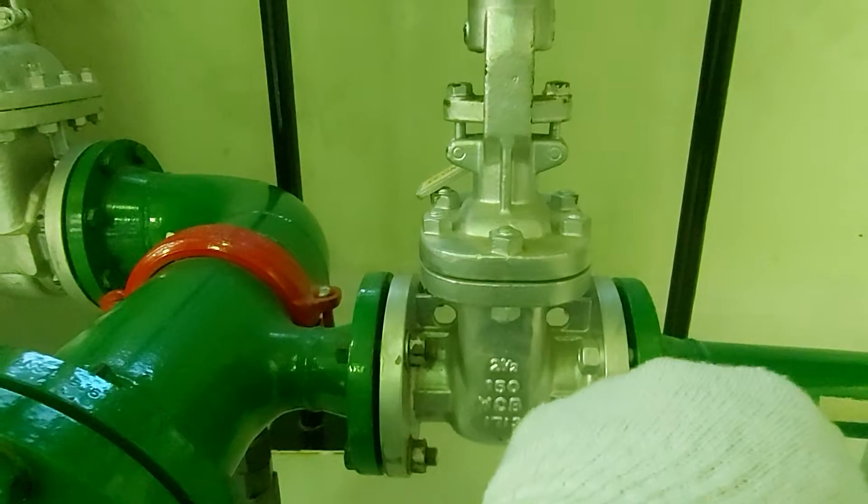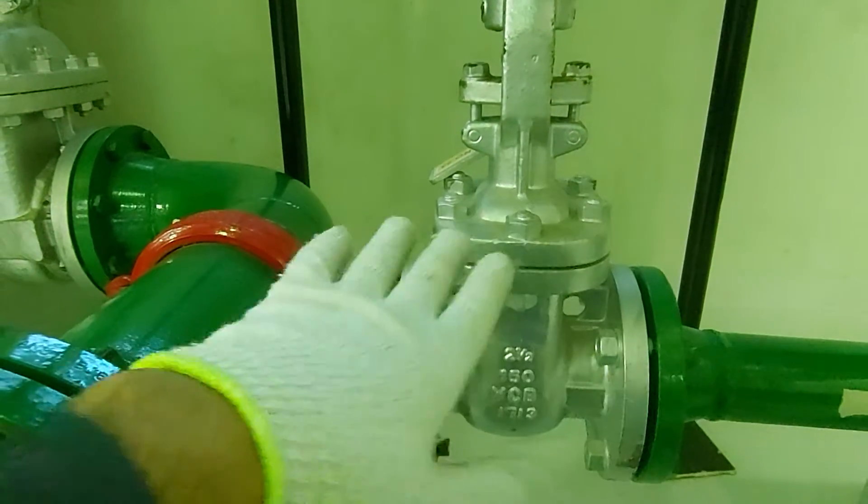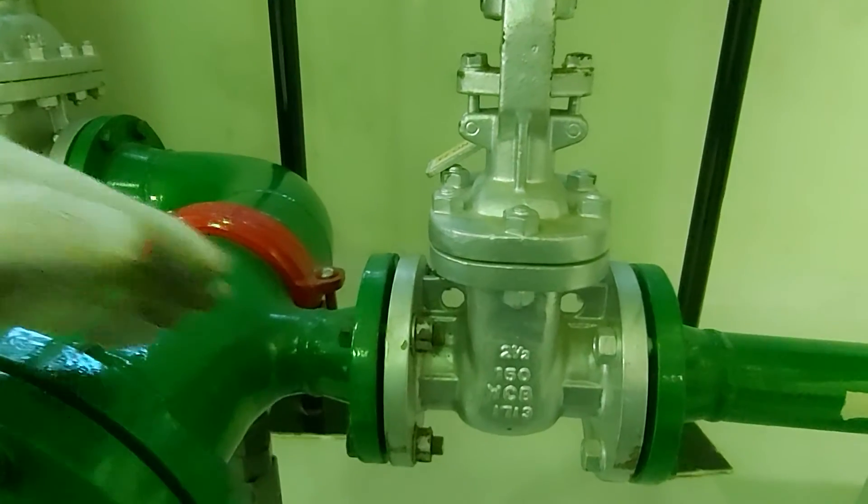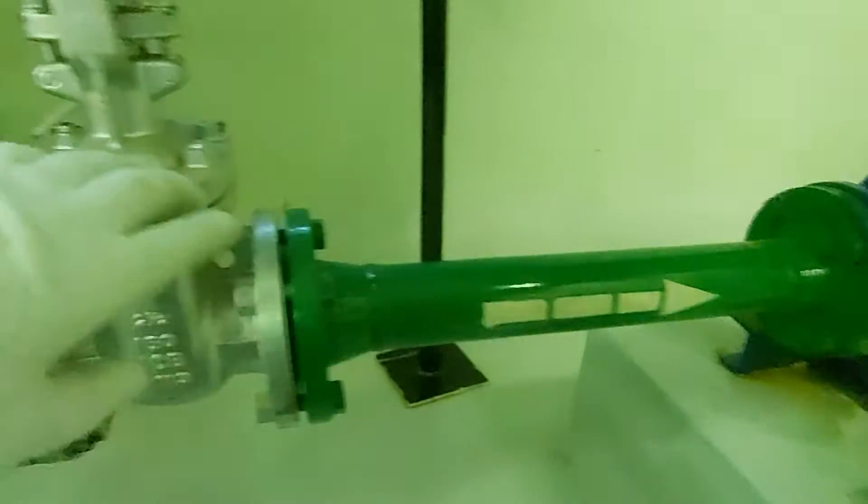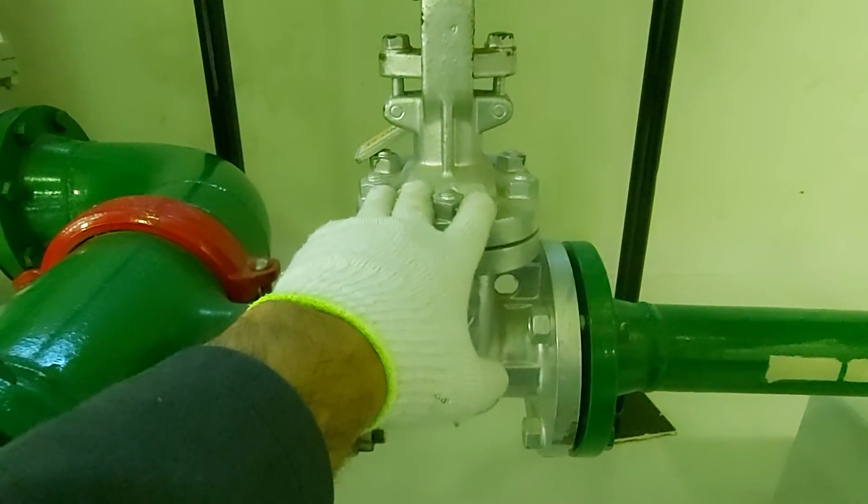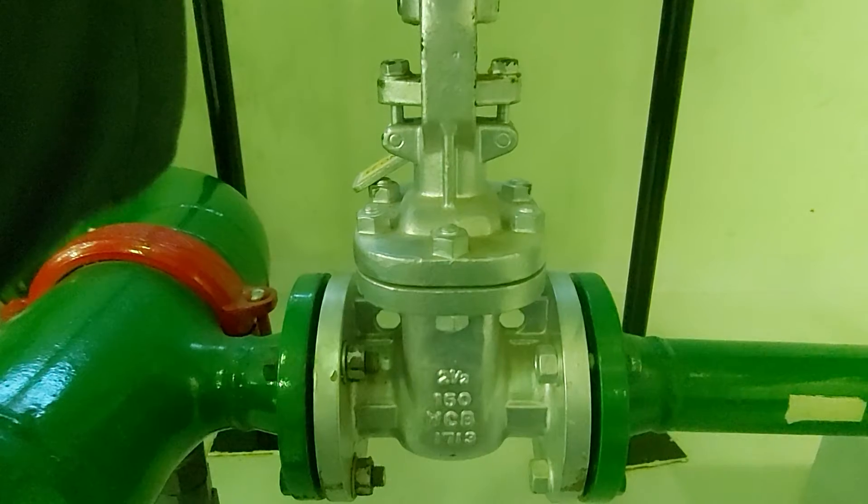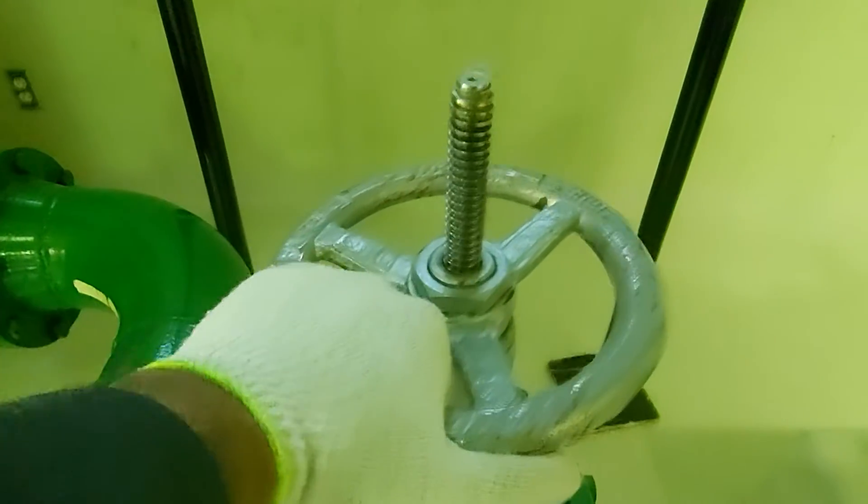In case of ball valve, we are opening it very fast, like 90 degrees, just rotate 90 degrees, it's fully open. So the liquid rushes and there is a back pressure which will damage the pump. So we use gate valve here. Why we use gate valve? Why it prevents fluid hammer? Because it has hand wheel, so when...